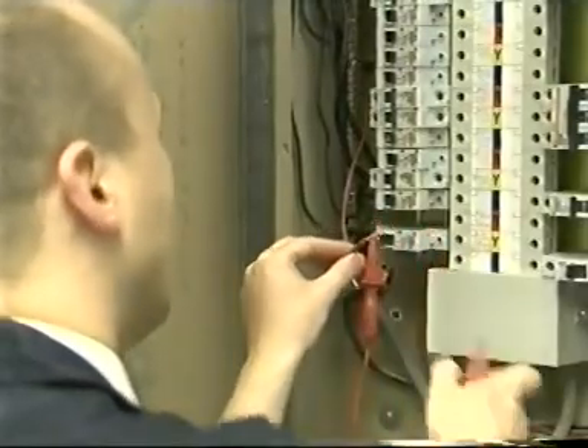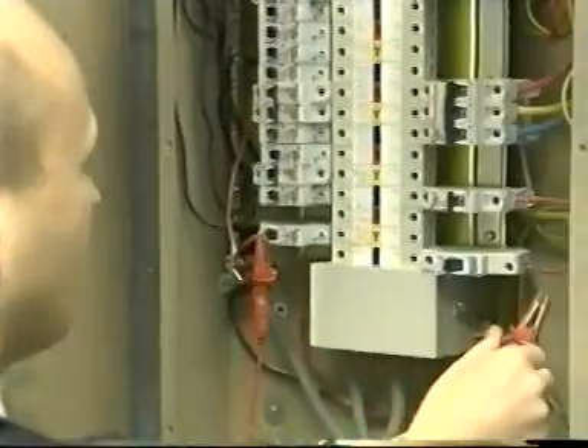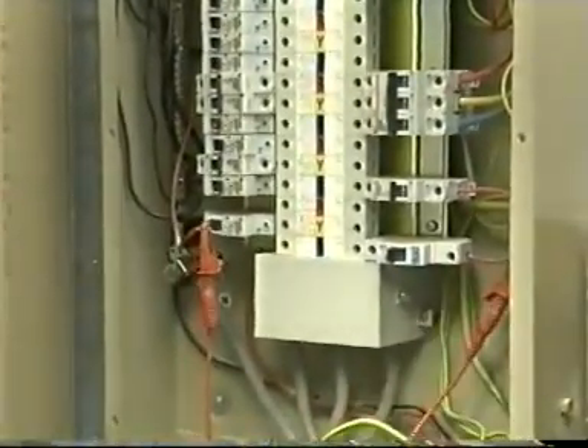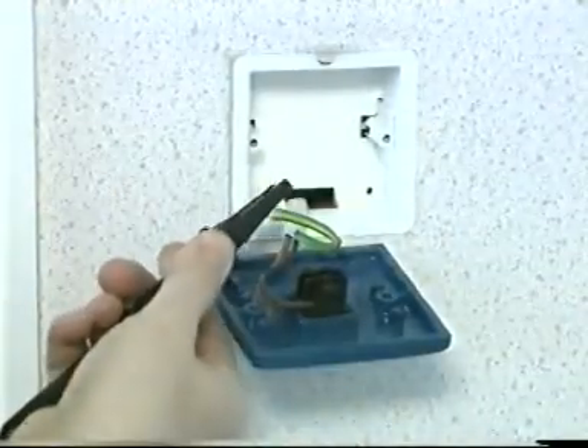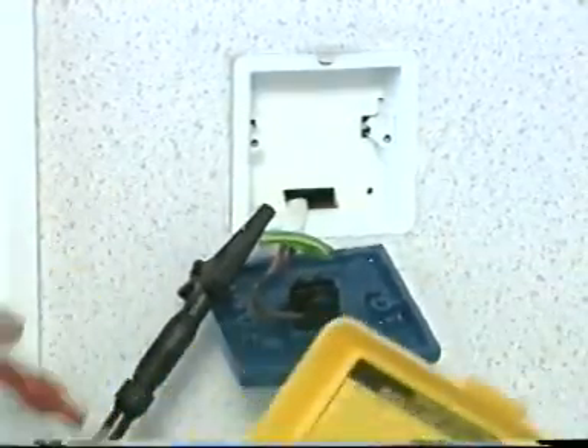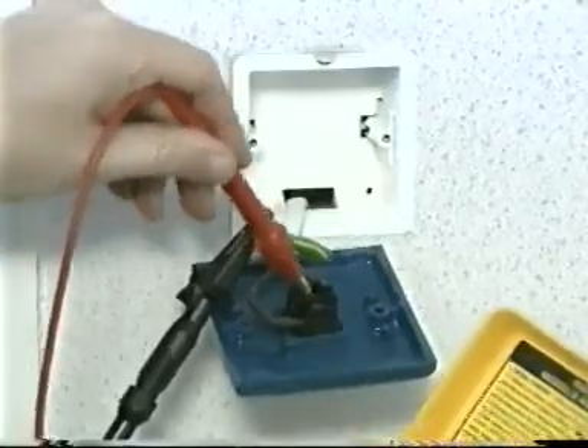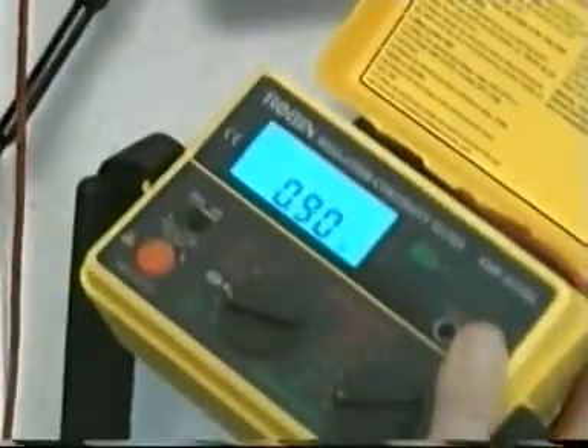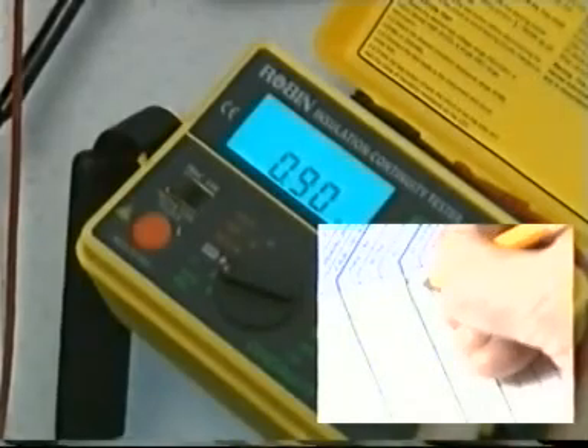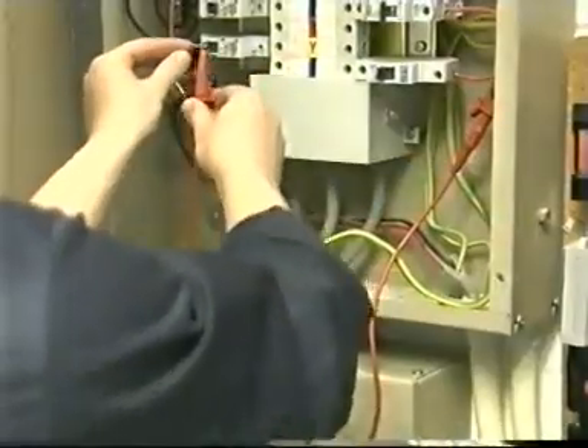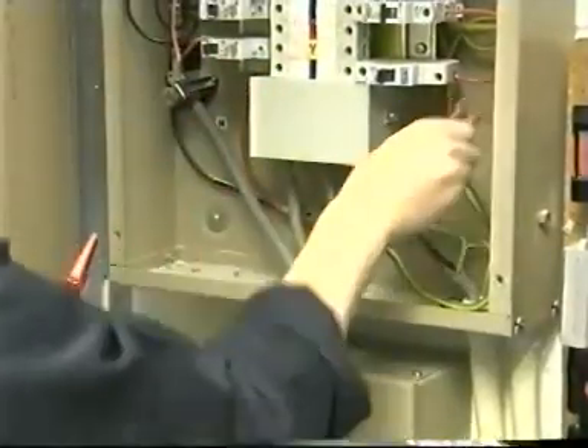A temporary link can now be made at the distribution board between the circuit phase and protective conductor. A test between phase conductor and protective conductor at the furthest point of the circuit will reveal the R1 and R2 for the circuit. The ohmic display between the circuit phase conductor and circuit protective conductor is recorded on the test result schedule. Remember to remove the link after testing.